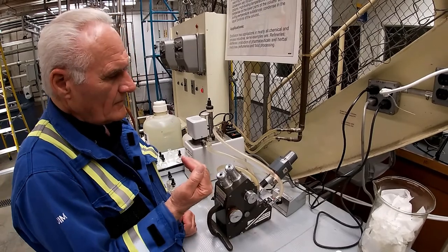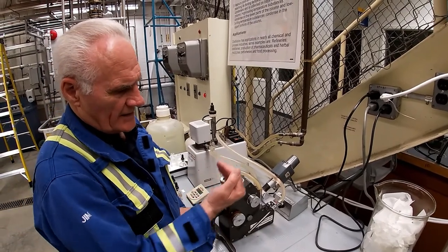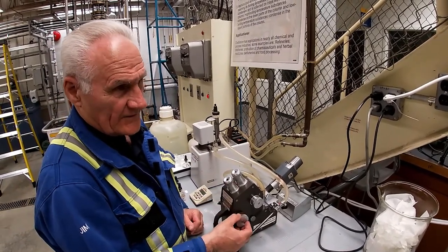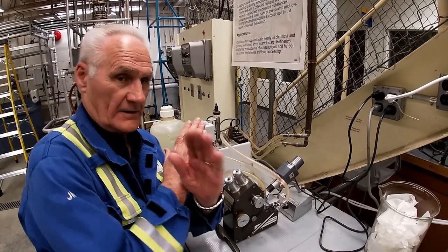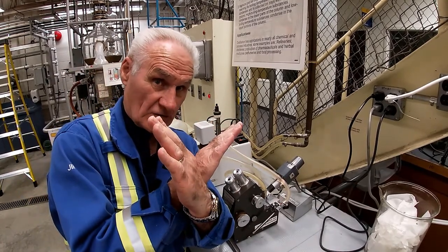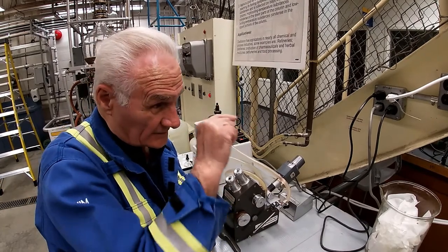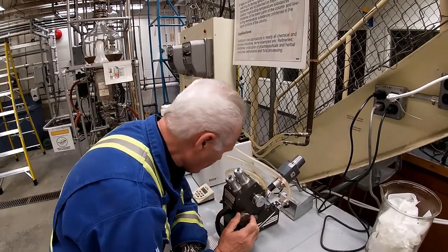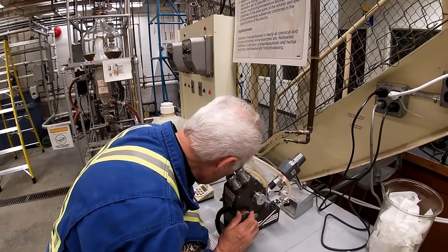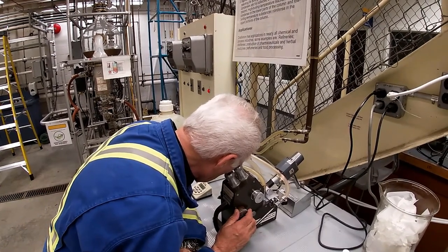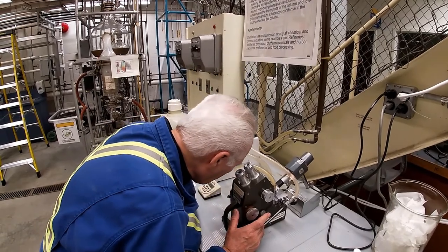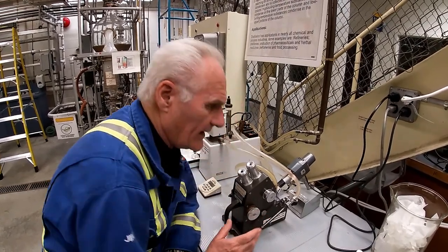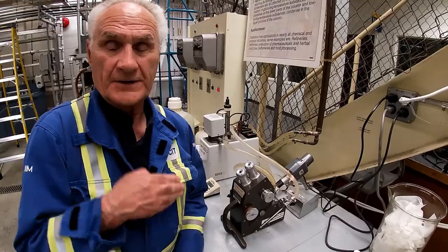Now, we can move the black line up or down with this refractive index dial. So what you do is you move the black line up or down till it covers the crosshairs. So there's crosshairs down in there, and I've got to line that right across the center of the crosshairs. So I'm adjusting it right now. You get it? And then I've got to read the refractive index, and I need a piece of paper.